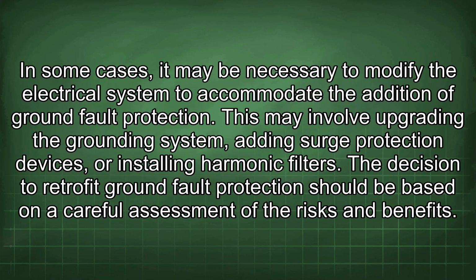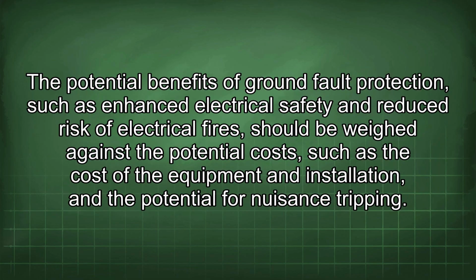In some cases, it may be necessary to modify the electrical system to accommodate the addition of ground fault protection. This may involve upgrading the grounding system, adding surge protection devices, or installing harmonic filters. The decision to retrofit ground fault protection should be based on a careful assessment of the risks and benefits. The potential benefits of ground fault protection, such as enhanced electrical safety and reduced risk of electrical fires, should be weighed against the potential costs, such as the cost of the equipment and installation, and the potential for nuisance tripping.